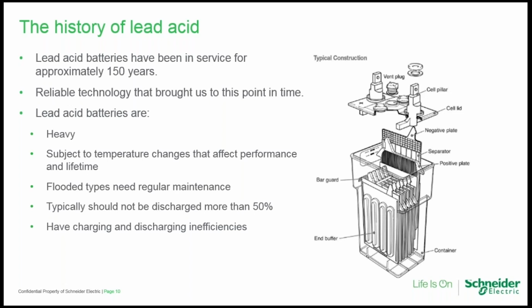Another thing that's exclusive to lead acid chemistries is the 50% discharge limitation. When you go below 50%, that's when sulfation occurs. That's not such an issue if you have flooded batteries because you can equalize them to recover their performance. However, they're not as efficient as other chemistries either, so you're going to get more losses when you're charging and discharging a lead acid chemistry.